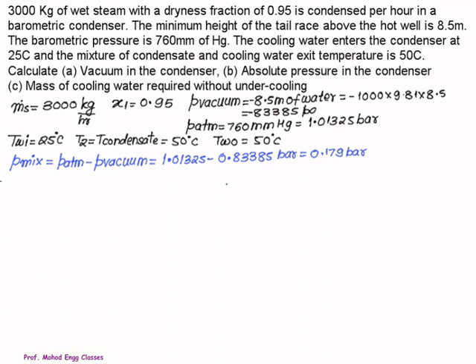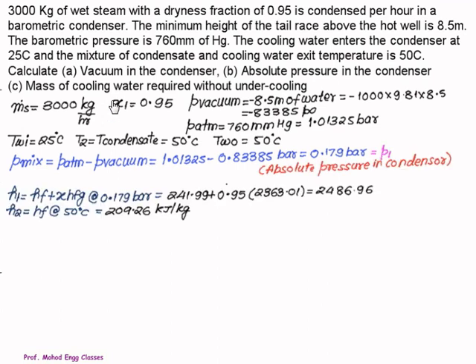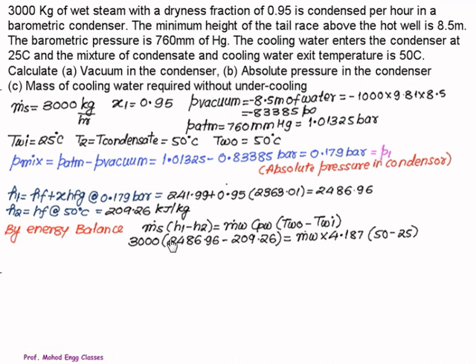We can record this value of 0.18 bar from steam table. To find the mass of cooling water we need to take the heat balance. For this we should know the enthalpy at inlet and enthalpy at outlet. Since the steam is wet, we will use the formula H = HF + X*HFG at a given pressure of steam, that is 0.179. Using steam table we get this value H1 = 2486 kJ/kg. At outlet of the condenser the temperature of the condensate is 50, so H2 equals HF which is 209.26 kJ/kg.